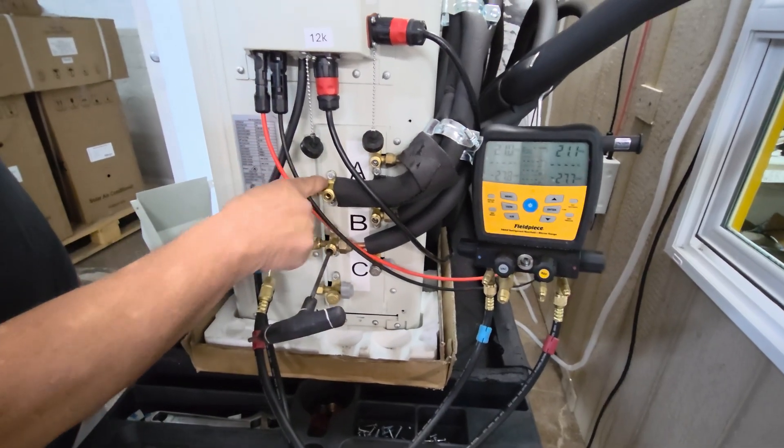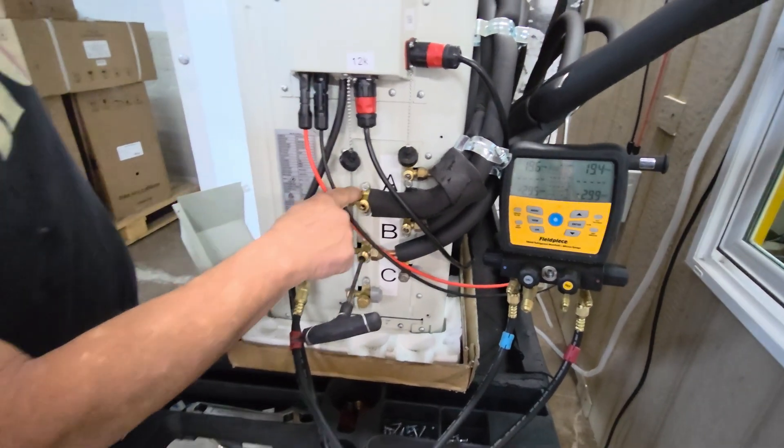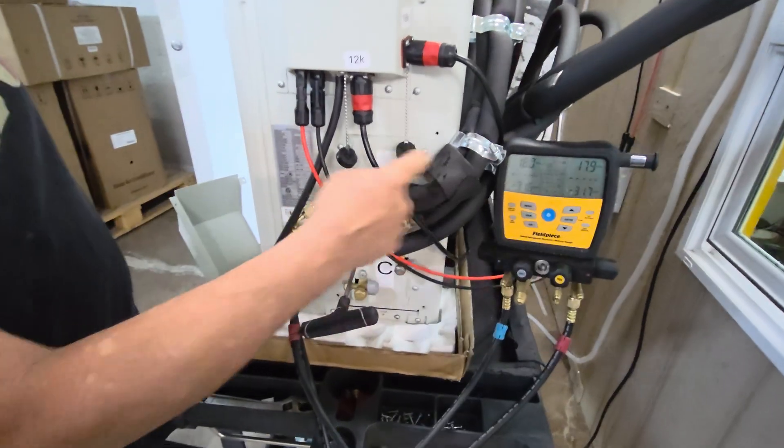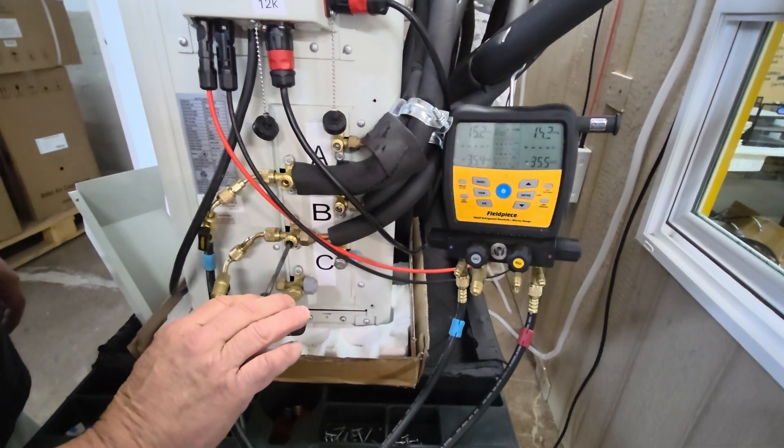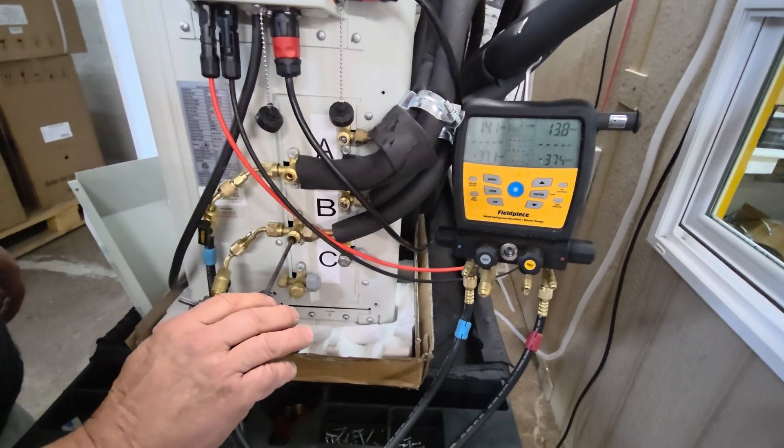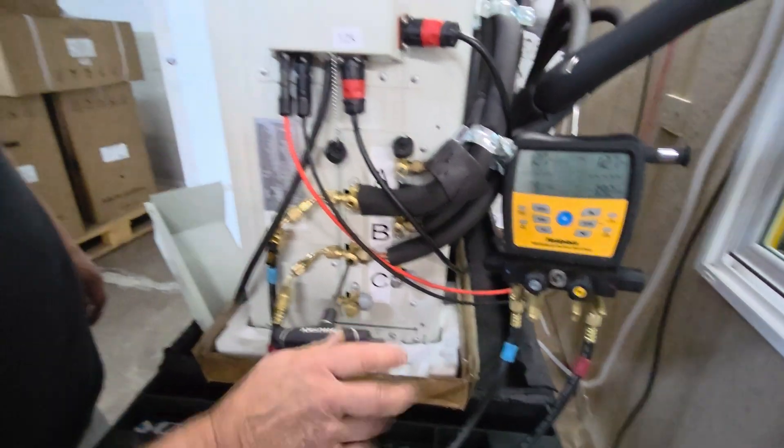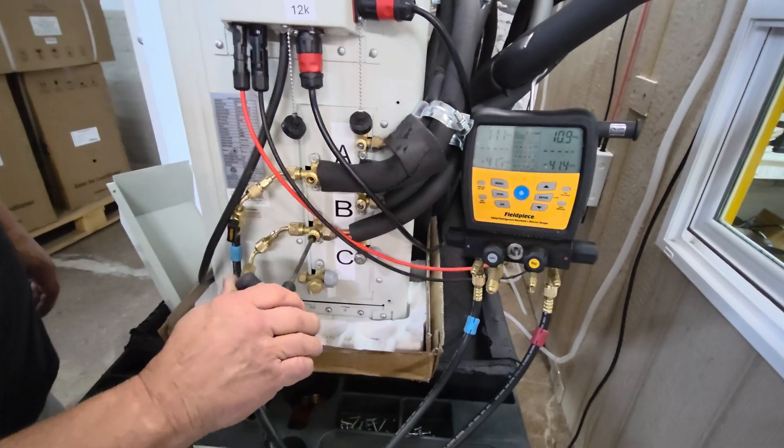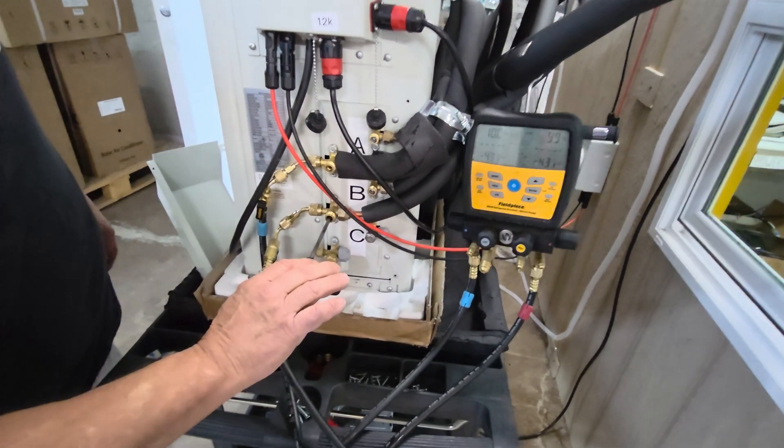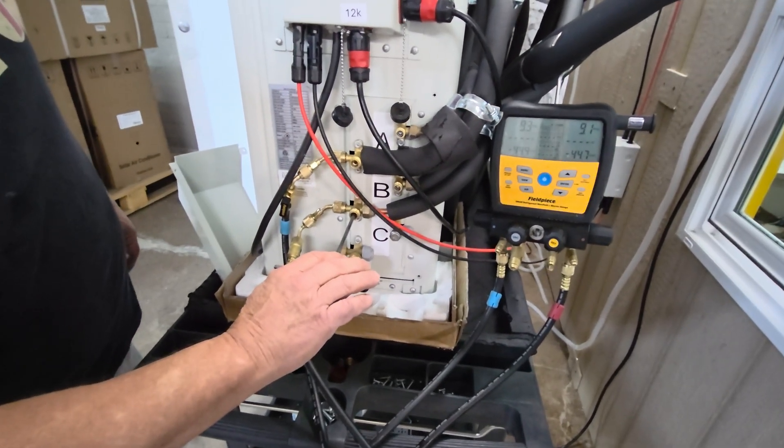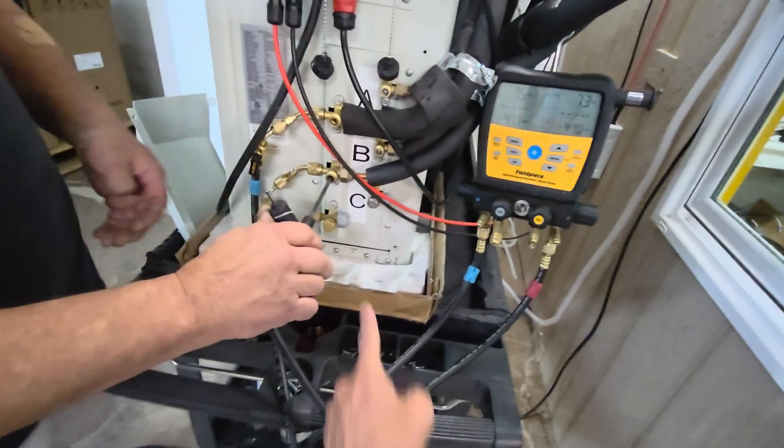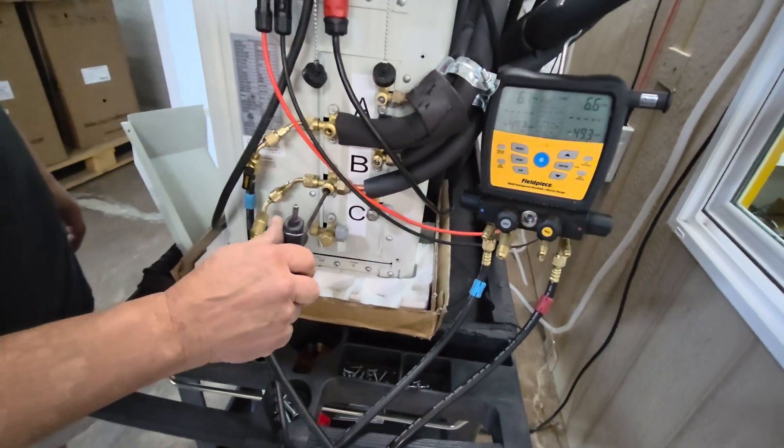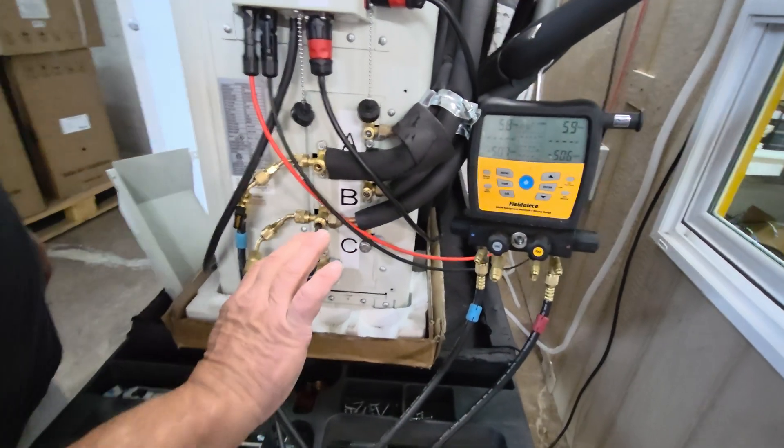In other words, you really only need a hose or gauges hooked up on this one port right here because they're pretty much the same. So if you don't have one of these fancy Fieldpiece gauges, your normal gauges will work on one line because they're pretty much the same. And this would work for three, five, whatever number of zones, as long as they're all in cooling.